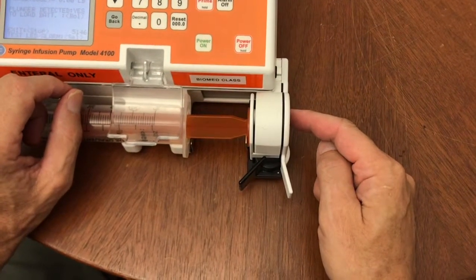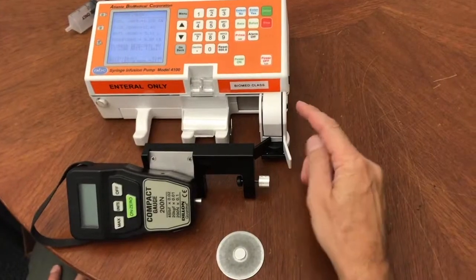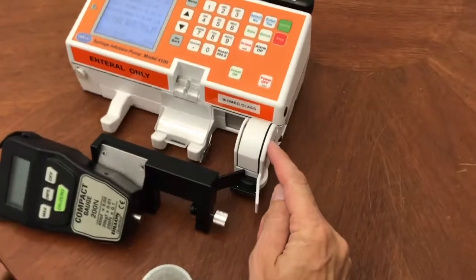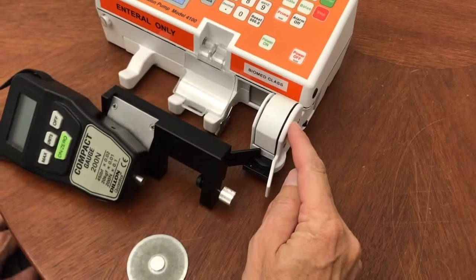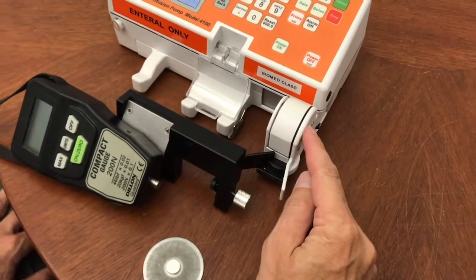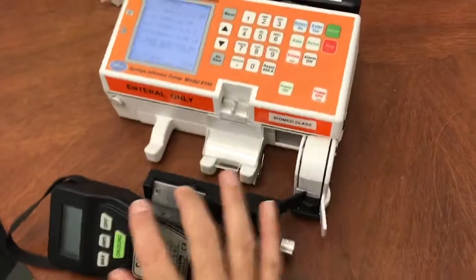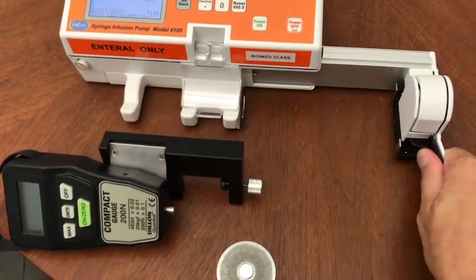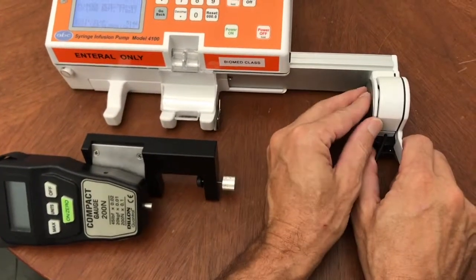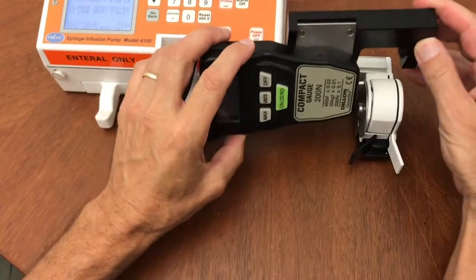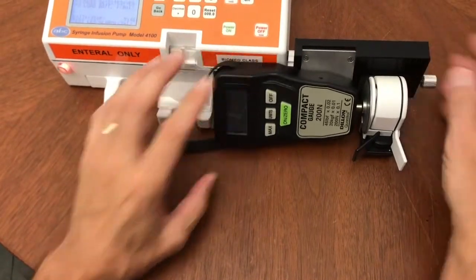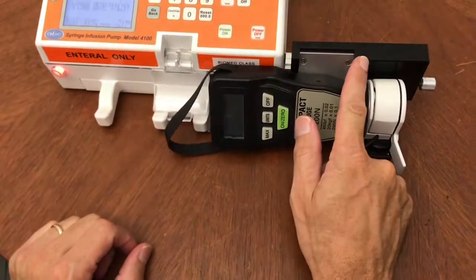sensor on the board. Since that socket head screw for the retainer assembly was loosened to replace the lever and then retightened, the force needs to be checked and or calibrated correctly with the force gauge and fixture.